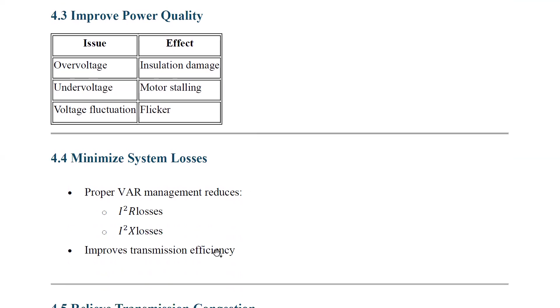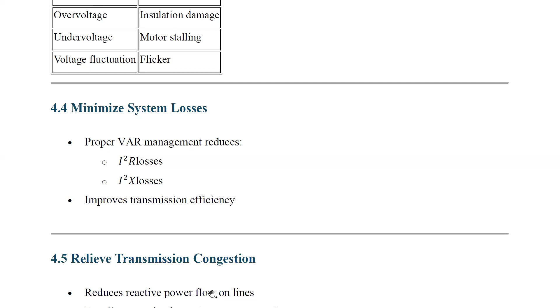Next, it minimizes the system losses. Proper VAR management, that is reactive power management, reduces the I squared R losses as well as the I squared X losses, and also improves the transmission efficiency. If you improve the reactive power, automatically the transmission efficiency improves and increases. So it relieves the transmission congestion.